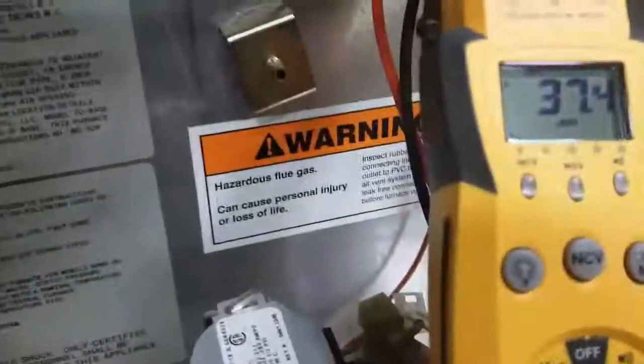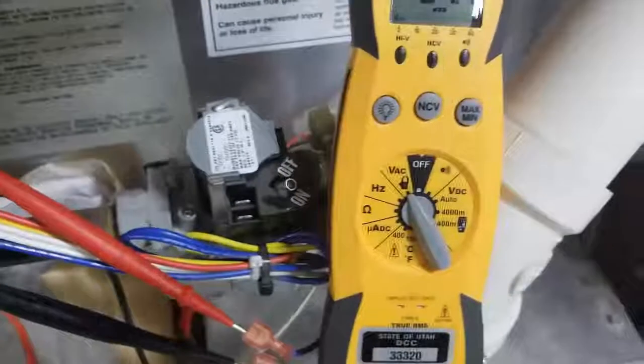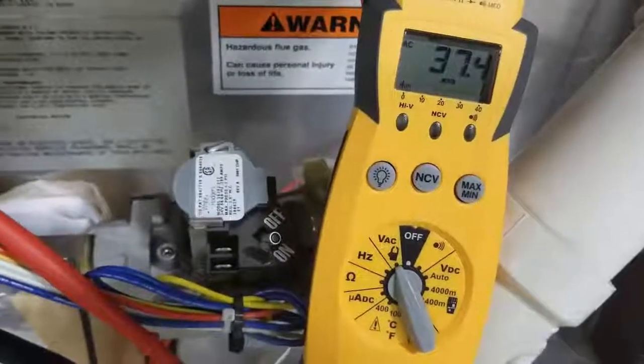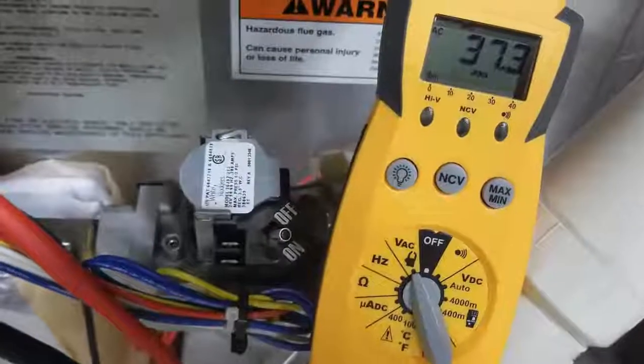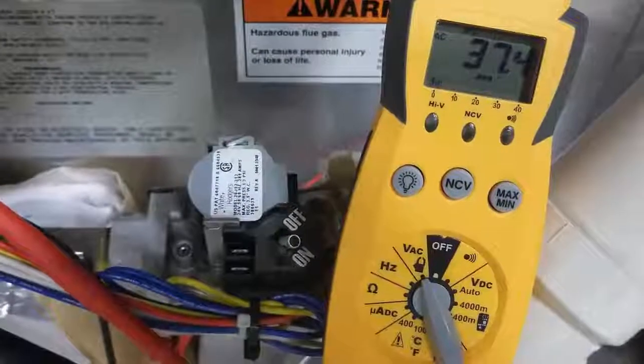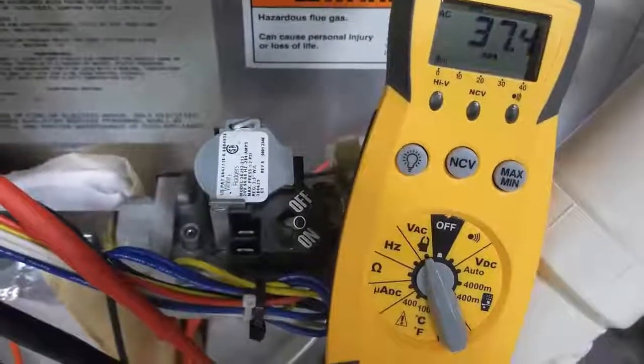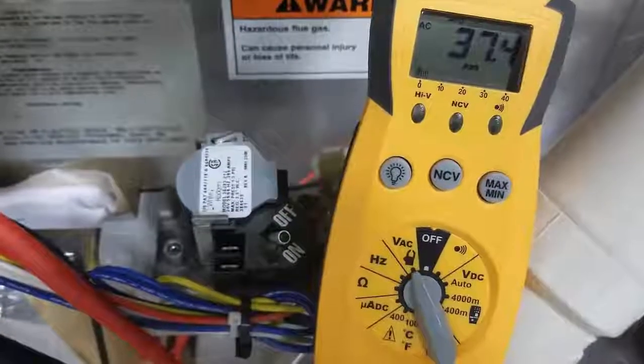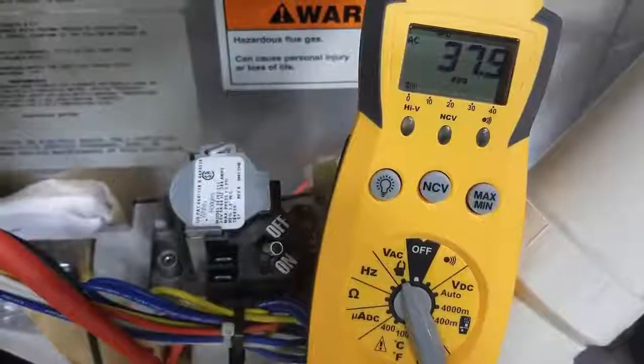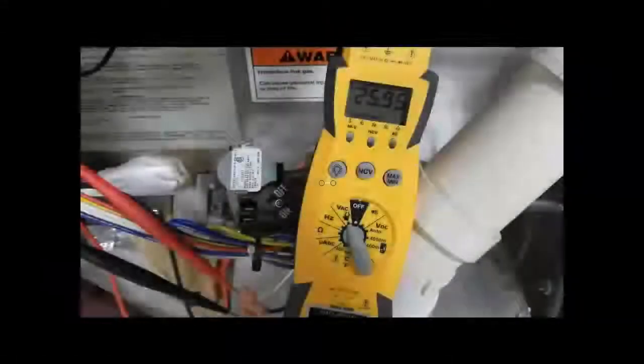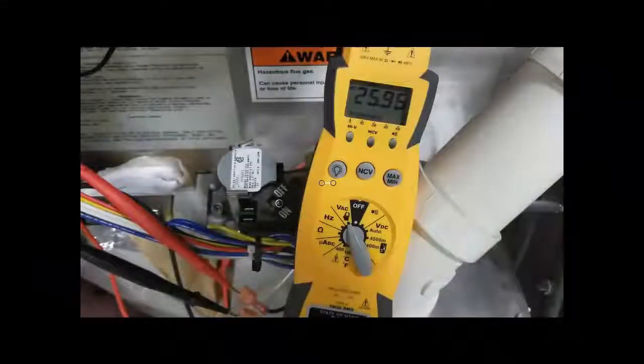Okay, you can hear the inducer motor running. What we're looking for here is 24 volts. Right now we're reading millivolts, which means basically no voltage. It's just small feedback voltage through the system. Okay, after 15 to 30 seconds of inducer runtime, we should get power to the gas valve. We're looking for 24 volts, plus or minus 3 or 4 volts. You can see here we've got 25.9 volts. So we know we're getting power to the gas valve.